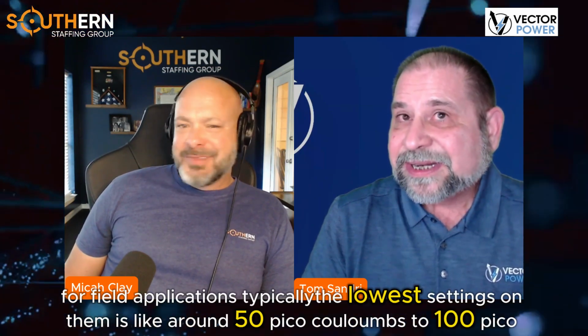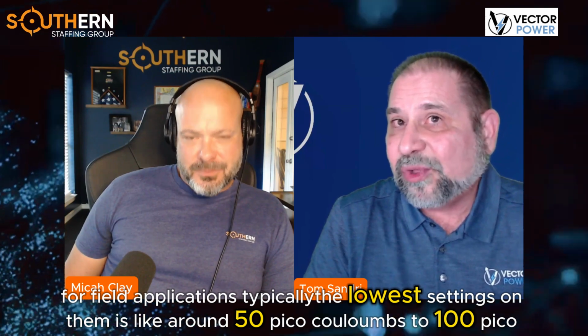Particularly when the pulse calibrators they sell for field applications, typically the lowest setting is around 50 to 100 picocoulomb. I'm sure if you wanted to buy one to a 5 picocoulomb level, they're available on the market, probably more typically utilized at factories and so forth. But again, if you're making that claim, I would like to see the evidence. I would like to see the supporting waveform captured from a field application where you injected 5 picocoulombs, it went a mile, and had enough energy to reflect all the way back to your receiver, and you're showing me the full length of cable with 5 picocoulomb.